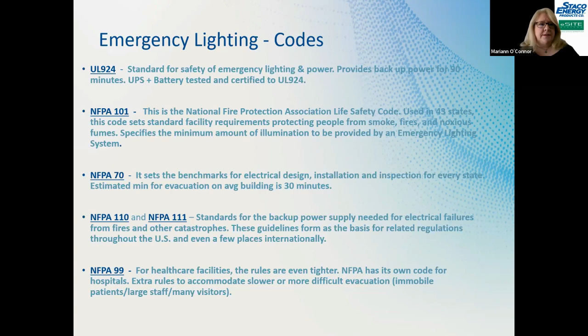Next slide, please. I just like to put up the emergency lighting codes. Primarily, we deal with the UL 924, which again states that for 90 minutes, the lights will stay on. That NFPA 70 is also for something that we also deal with. It's for the system, and the average time is 30 minutes. Then there's one for healthcare facilities. So it's kind of just good to know the codes that are out there and which markets they service and address. So next slide.